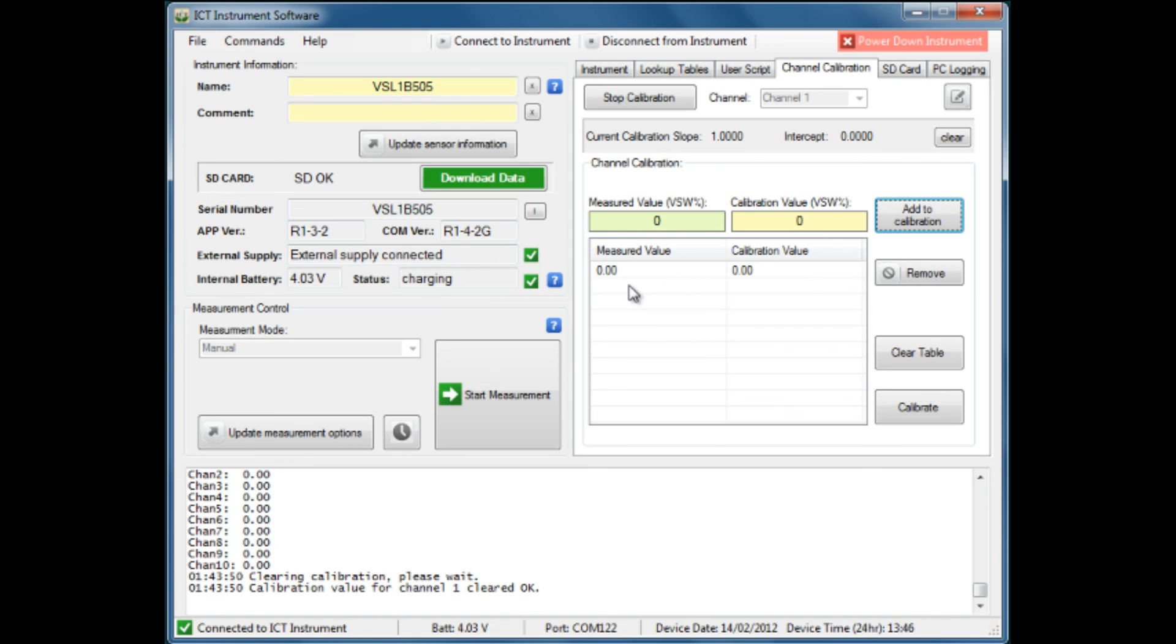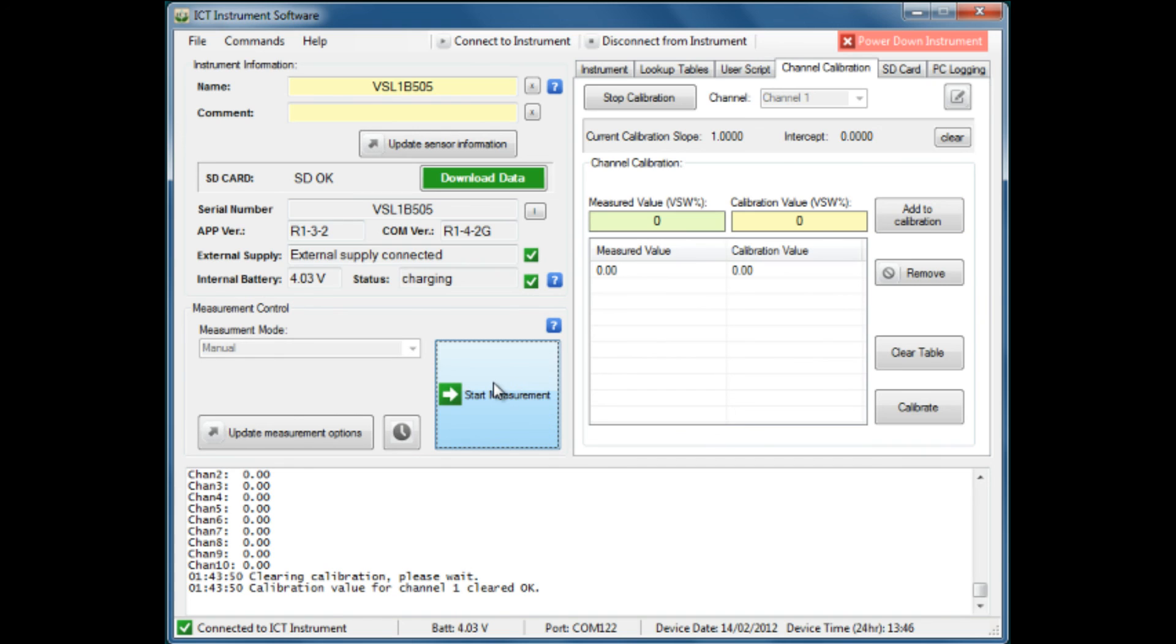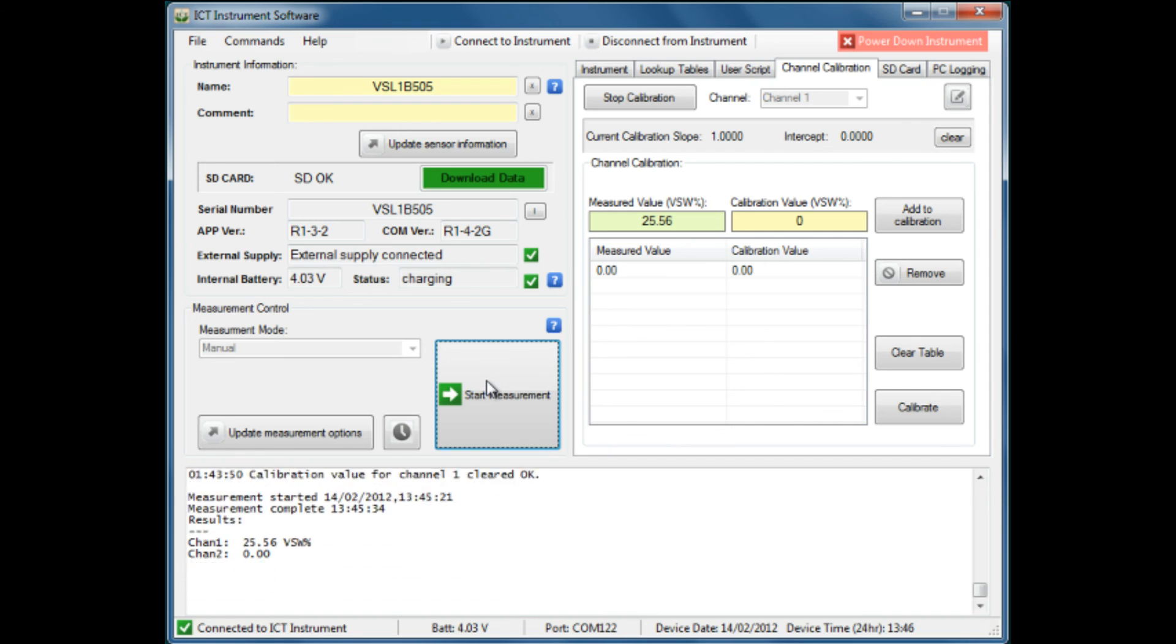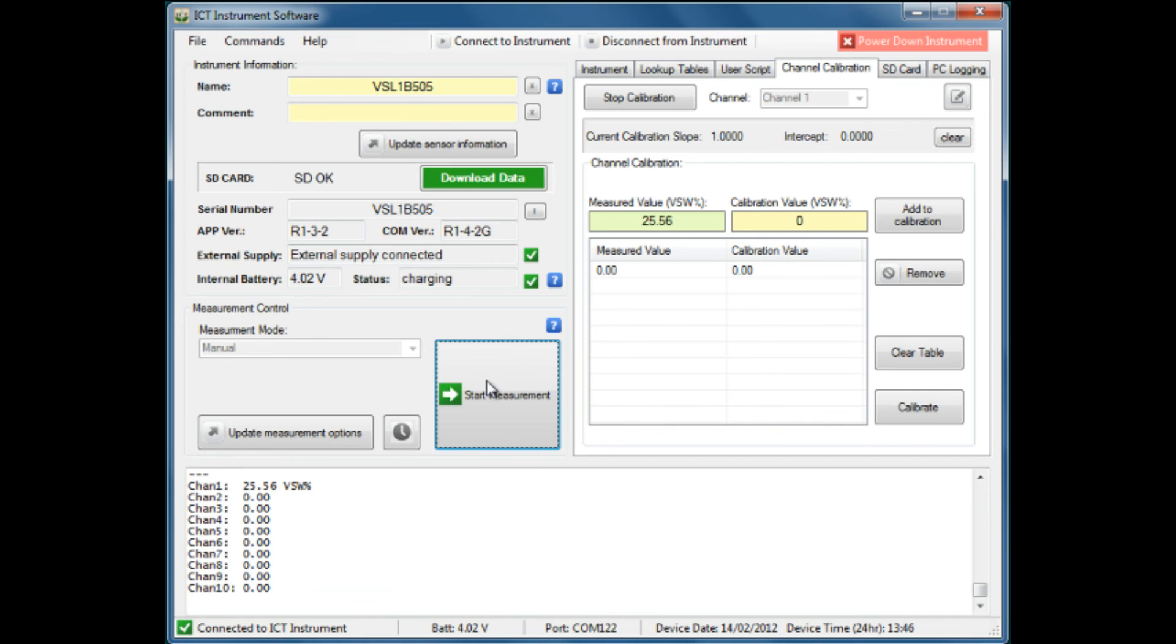To do a reliable calibration, we actually need three sets of values to use, and that's our first set. In the second set, we will actually take a measurement. We start the process, and the instrument connects to the particular sensor and takes a measurement in our reference soil that we're using. It's come up with a measured value of 25.56.